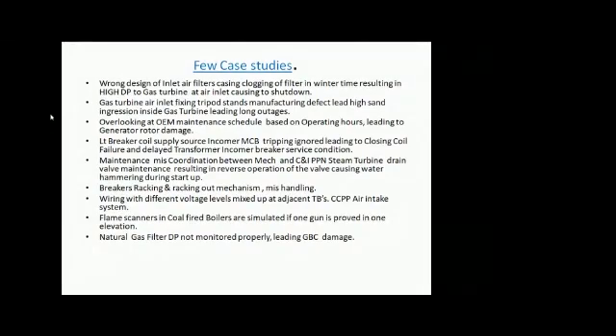But a mistake had happened, and at the time of starting the steam turbine, there was a huge water hammering. Suddenly we did not know how the valve was operating. We were getting feedback. But while doing the refixing, the mistake was that, while removing the actuator, the open position of the valve was not properly marked. Open and closed positions of the valves have to be properly marked. If they are not properly marked, then while fixing it back, a mistake can happen. The actuator is fixed in the reverse direction. Instead of opening the valve, it is closing the valve.